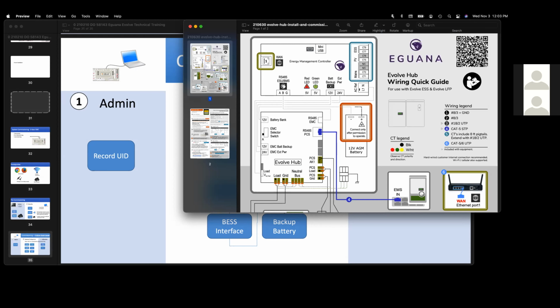From Tafara: is it correct to say the Evolve Hub is basically a battery inverter? No, the Evolve Hub is like a gateway. It's an energy management system. The hub is the energy management system that connects the actual battery system, which is the ESS or the LFP AC battery, to the grid. It connects the backup loads panel and the PV to the grid, and it is the hub for communications and control and monitoring of the whole system, behind the meter visibility and control of the battery. So the hub itself is not the battery inverter. The battery inverter is in the Evolve LFP or the Evolve ESS part of the product.